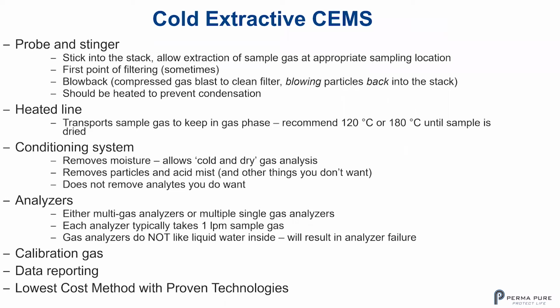Recommend 120 degrees C or 180 degrees C until the sample is dried later on in the sampling conditioning system. One of the reasons you need to go so hot is that not only do you have the water dew point, but you also have an acid dew point. You also have the point at which acids can condense, and that's usually above 120 degrees C or thereabouts, depending on your stack gas. And if those condense out, that's a real issue.